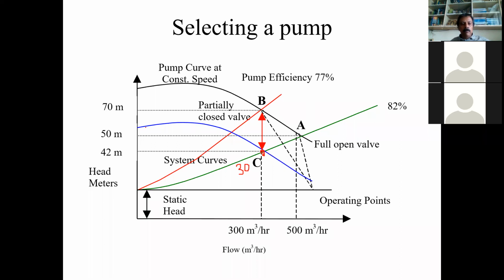Now, how to get this blue curve? We got a big pump. This is common in many industries. We find that the pump sizing is oversized, ultimately resulting in this kind of situation. So many of the plants prefer to run it in a throttled condition. In any case, it does not affect the process. The requirement is met, everything is going smooth and fine, so not much concern is there. So this requirement of some change in the pump or some change in the operating characteristics will be known only when you do a measurement.